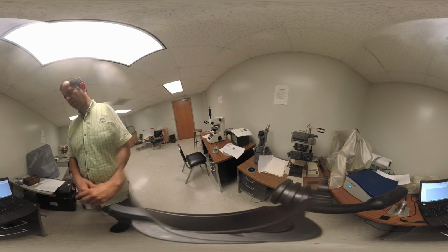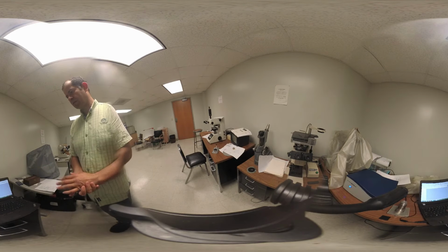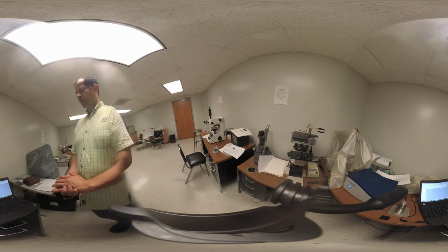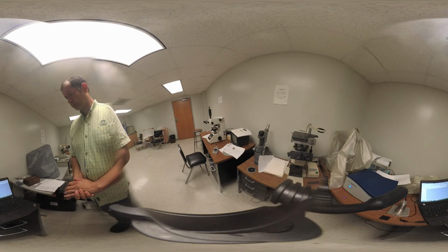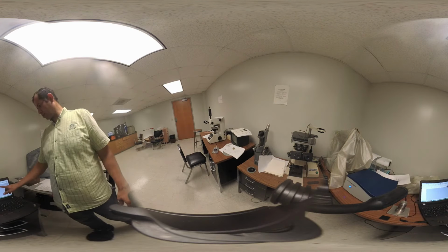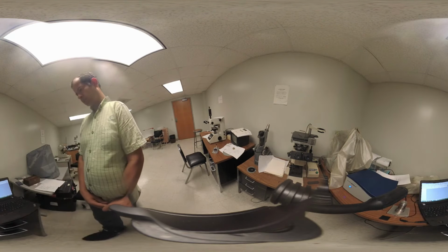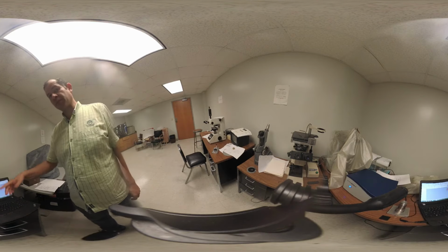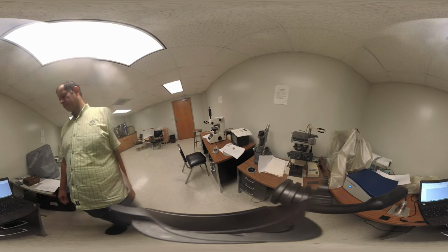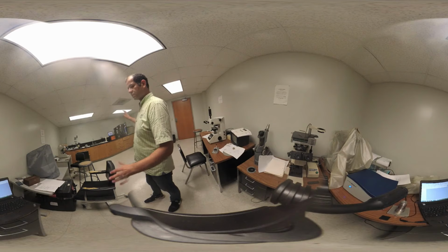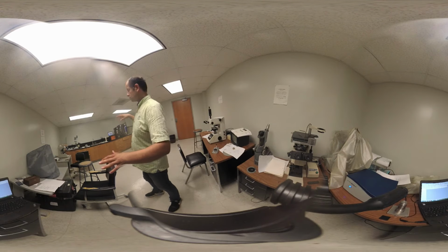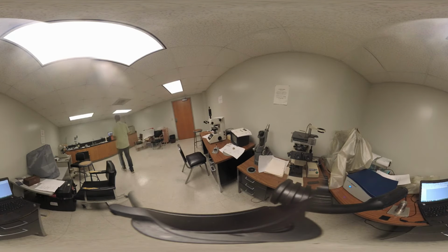Once I finish, I will save the data, take a picture, and send it to you. So delta T 1.6, ambient temperature 19.9. Always keep your eyes on it to make sure there's water, there's no problem here.